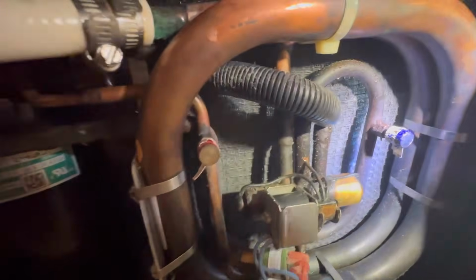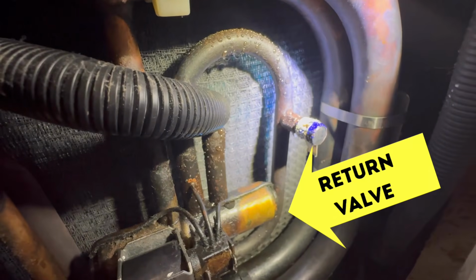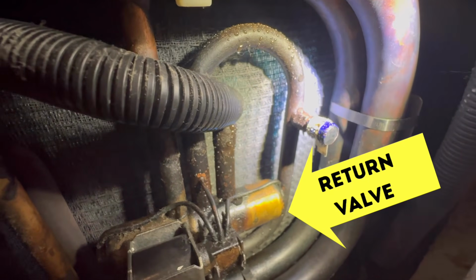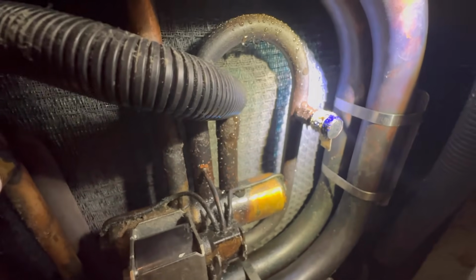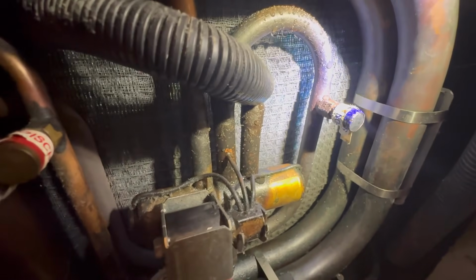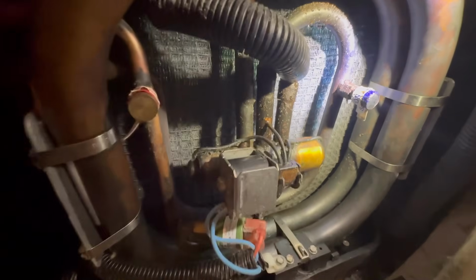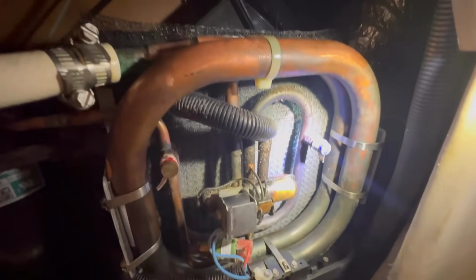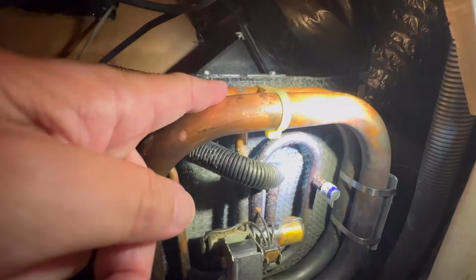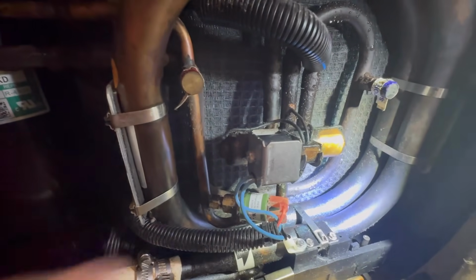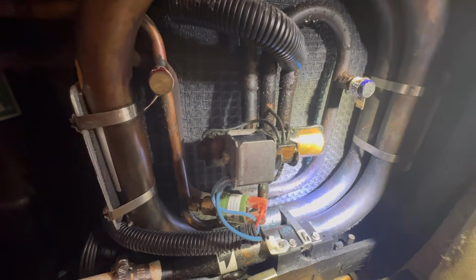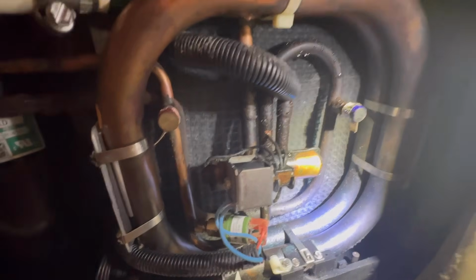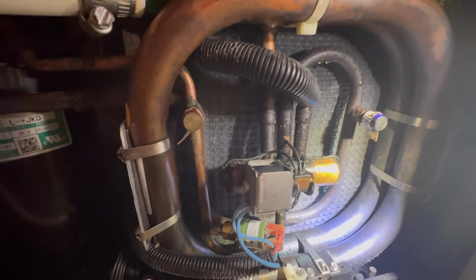If you take a look right there at the return valve, you might be able to see it - there's a little bit of liquid right there. It looks like maybe it's condensation, but that's actually where the Freon leak is. A telltale sign that you have a Freon leak: you can see the coils right here, they're copper, but if you look at the bottom right here, they're black. The reason they turn black is because the Freon leaking out has actually turned the copper black. So we've recharged this air conditioner twice.